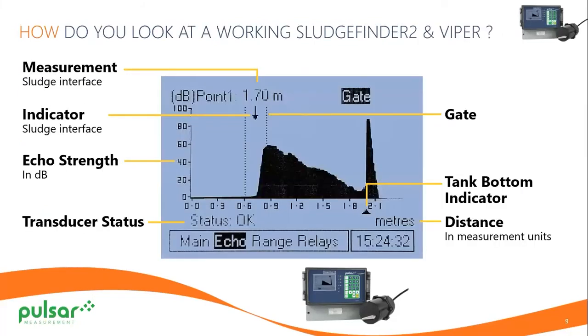How do you look at a working Sludge Finder and Viper? This is what you will see on the controller interface. At the bottom, you can scroll over to Echo, and looking at the Echo, you will see the measurement of the sludge interface, 1.7 meters. You have the arrow which indicates the sludge interface.